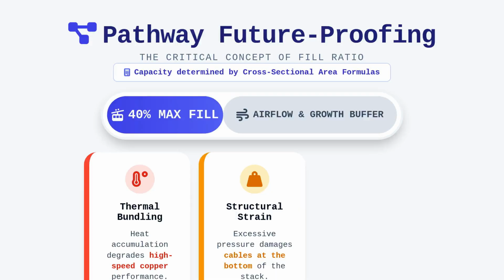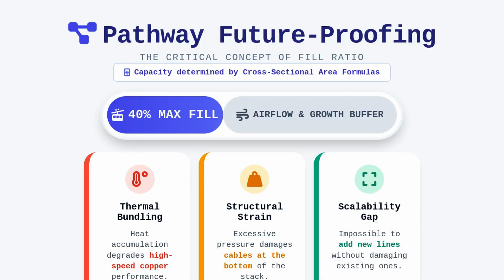When we fill a pathway beyond this limit, we restrict airflow, allowing heat to accumulate within the cable bundle and potentially degrading the performance of high-speed copper cabling. Furthermore, exceeding this capacity makes it physically impossible to add new lines in the future without damaging existing installations, thereby violating the fundamental principles of a scalable infrastructure design.